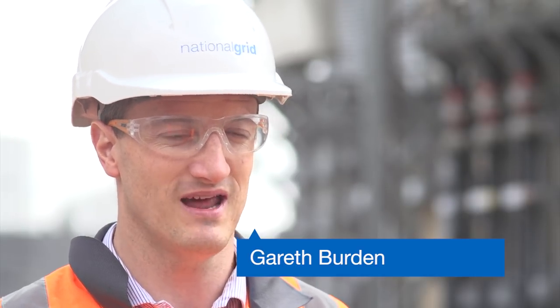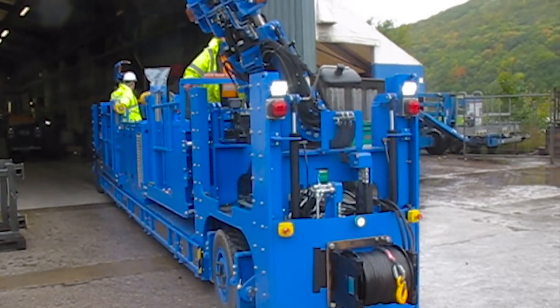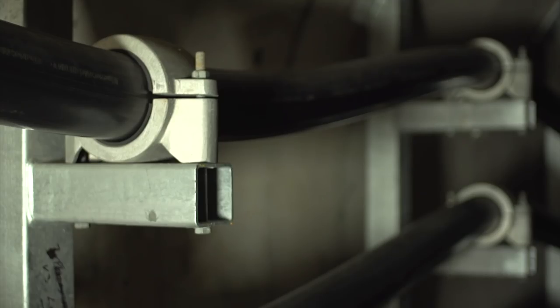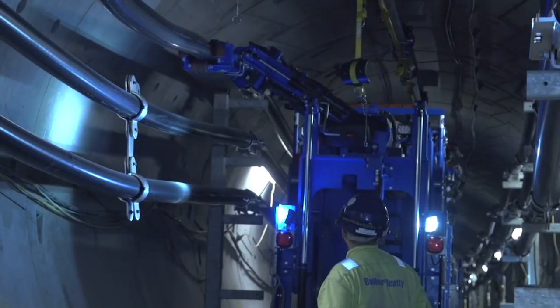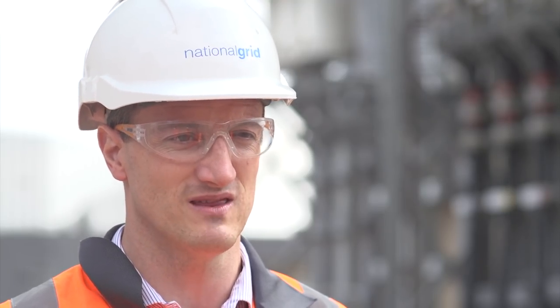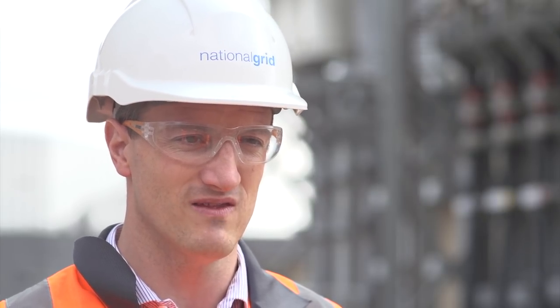Installing 200 kilometres of HV cable comes with its risks. There is a lot of stored energy and force in manipulating and moving that amount of cable around some pretty tight urban sites. Each cable is delivered from Germany and weighs somewhere between 35 and 40 tonnes. Those cable drums are then paid off down a tunnel shaft 30 metres below ground onto two specialised machines which tow the cable into its final position and fix it within the tunnel system. So far it has gone very well and we are very pleased with the technology we have employed.